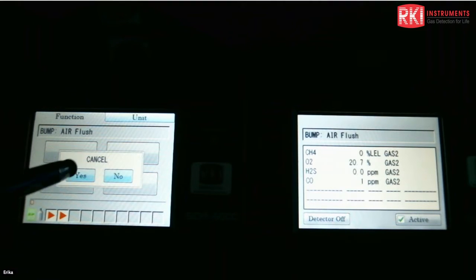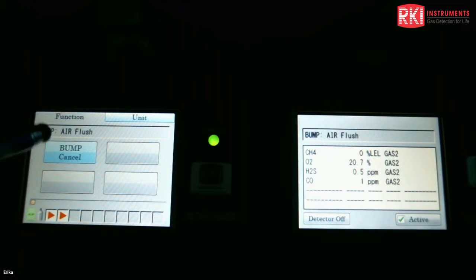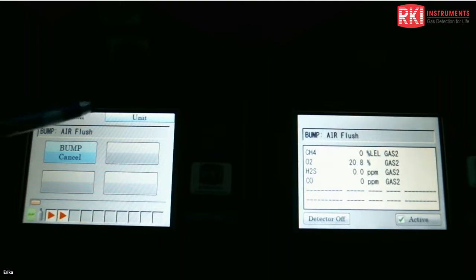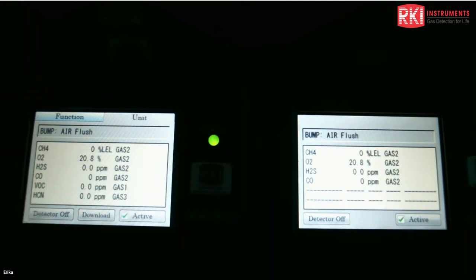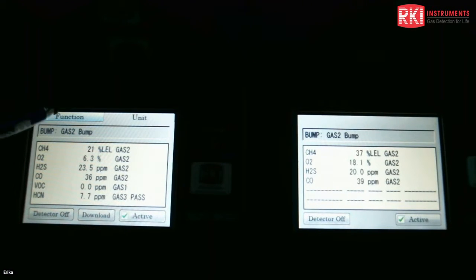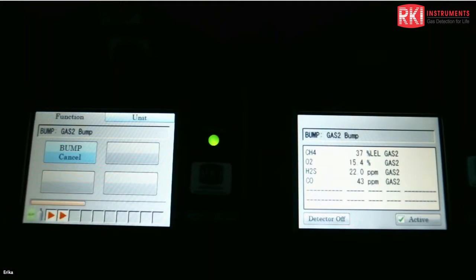Okay, so I'm going to do a bump test. Again, there's that bump cancel if you want to cancel it. And status is still going. It means it's going through both of them. You can also go through the Unit tab to see what's happening with the gases in real time. So gas 3 bump, and that one's skipping it because it's HCN, and it's running gas 3 first because it's HCN, which is what it's programmed to do. There's also that little progress bar over there.